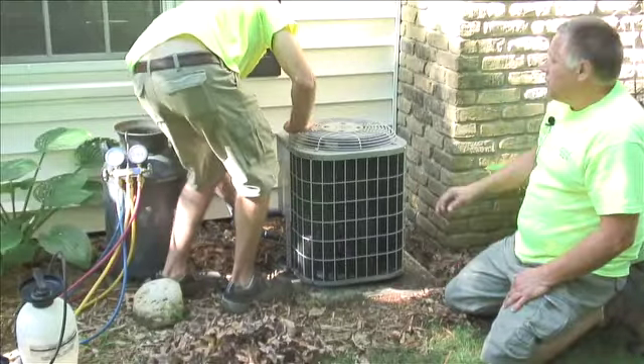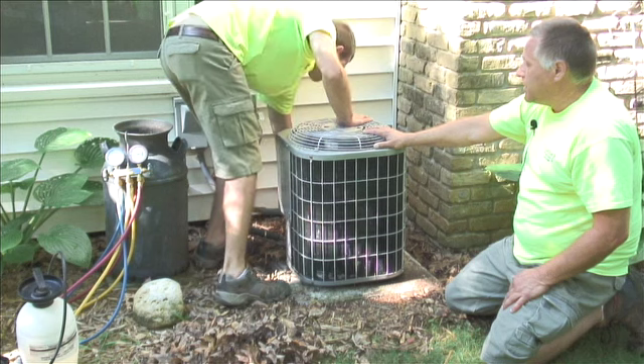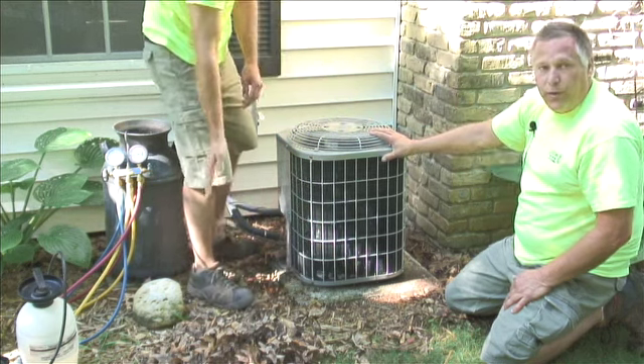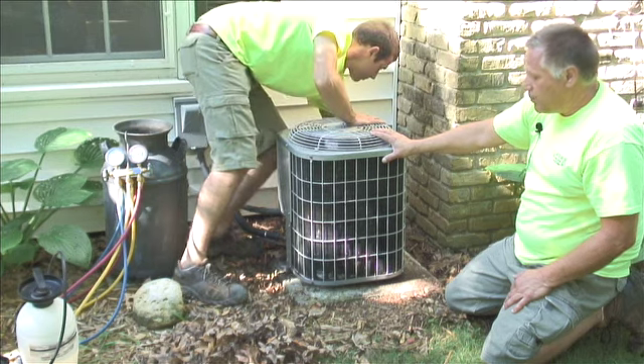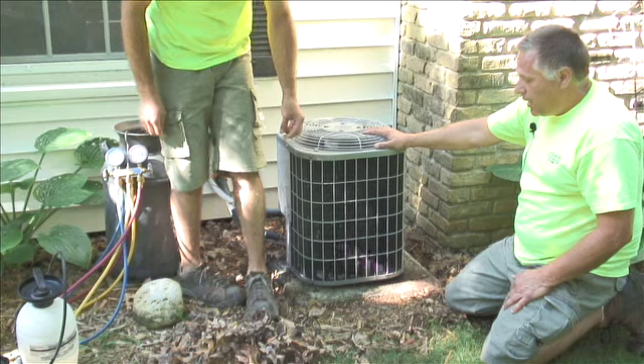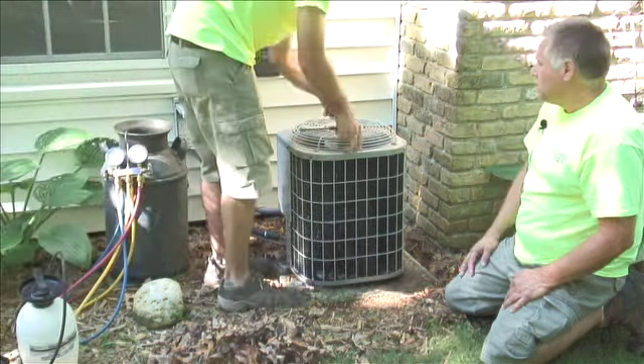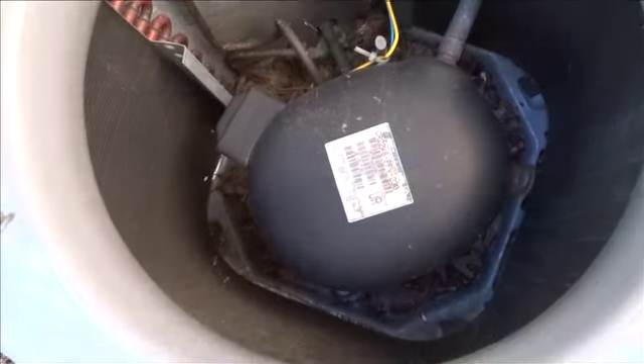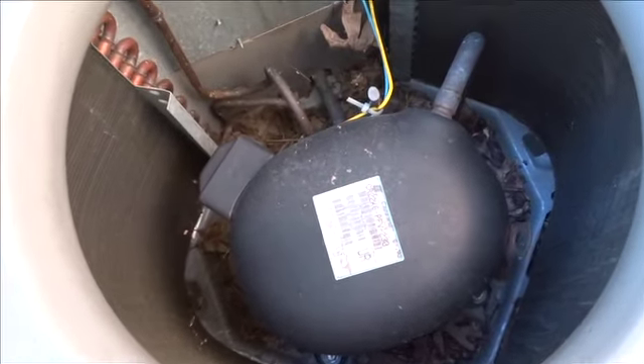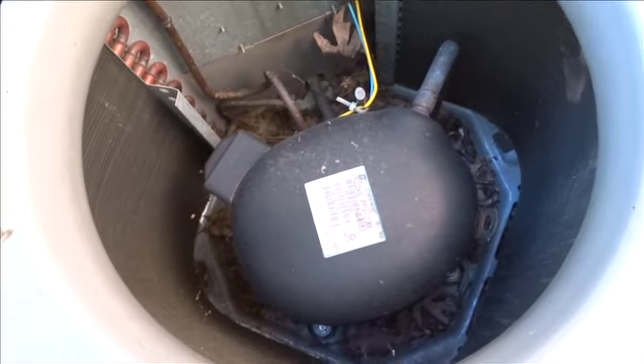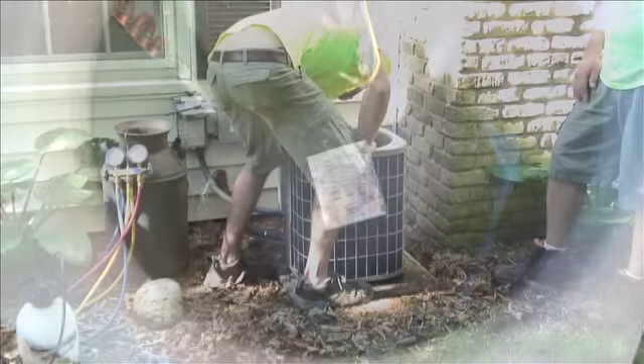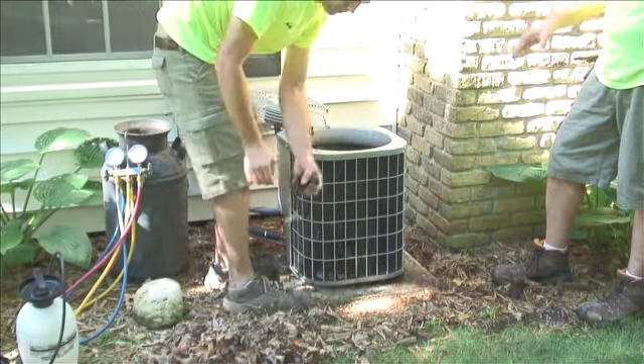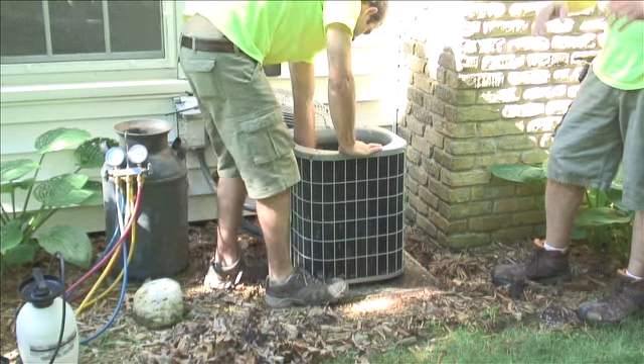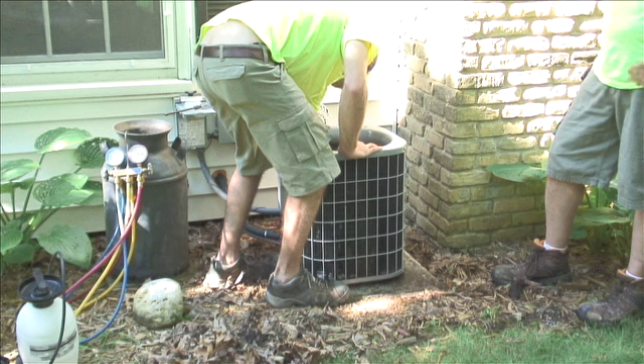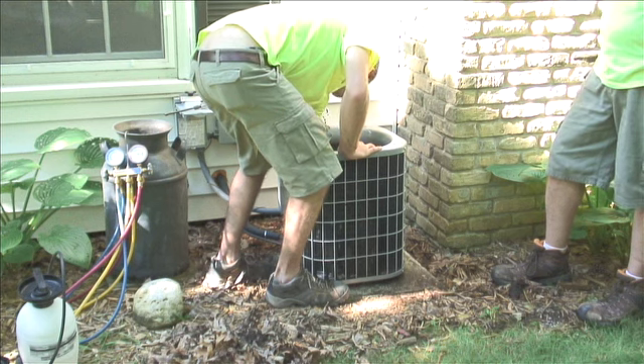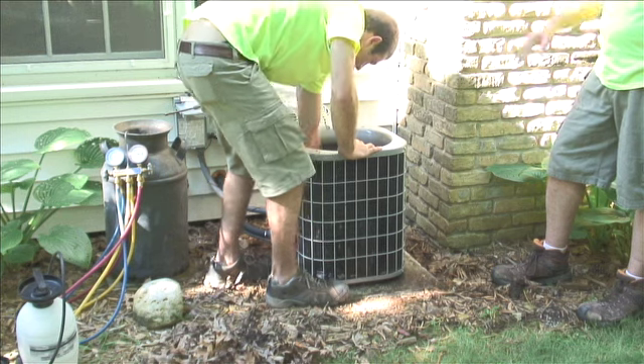After we do that, the next thing we check is the debris that has fallen inside the air conditioner. This tends to block up the drain holes and hold water inside, which stops the unit from draining properly and will cause it to rust out prematurely. It's very common to find mice and chipmunk nests. They like to go in there and chew the insulation off the wires over the winter time. Quite a few jobs we've opened up and actually found a whole mouse nest and family living inside, with the coating on the wiring all chewed off, and it tends to short all the electrical components out inside the unit.